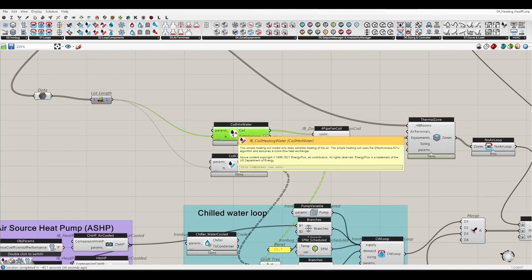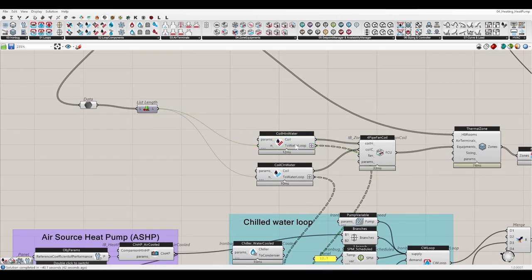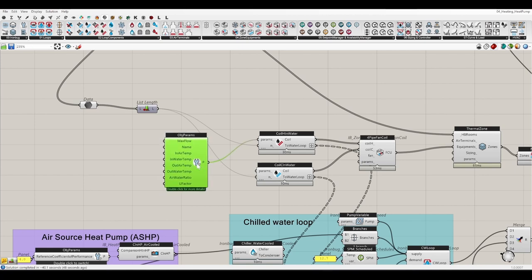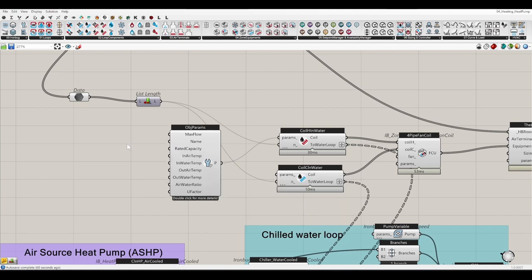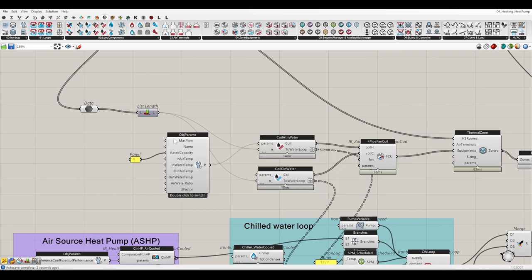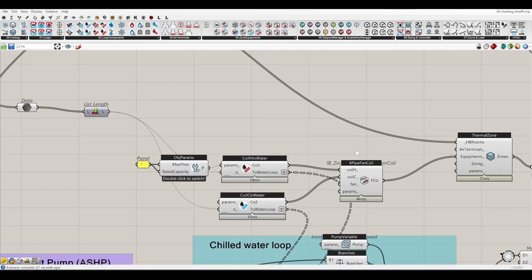I think we can hard-size the heating coil to zero so it doesn't use the system at all. Let's see if we can set the heating capacity to zero, and also maximum flow rate to zero, in order to turn off the heating coil — because we are going to use a baseboard for the heating instead.